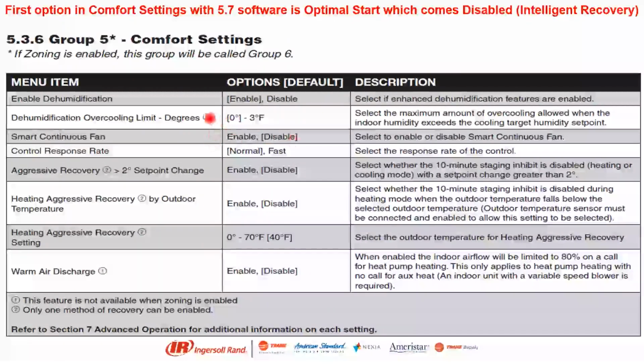Group 5 comfort settings, enable dehumidification. That's enable or disable. Again, if you have it, you're going to enable it. Smart continuous fan, you've got your control response rate, aggressive recovery. We don't recommend enabling that in dual fuel applications because it's going to turn on the gas furnace quicker. But when you have a heat strip, it'll take 15 minutes to engage that heat strip. So if you enable that, it'll bypass that 15-minute time.